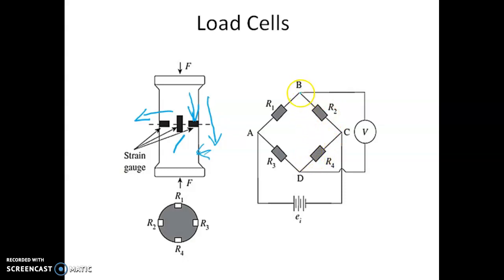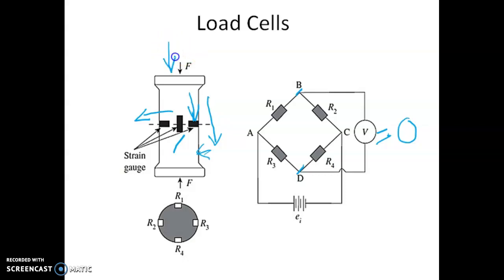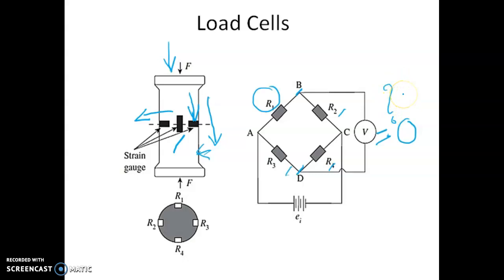The potential difference is taken between points B and D. When the elastic member is at the initial stage and not loaded, the potential difference will show a voltage equal to zero. When a compressive load is applied, the resistance values of R1, R2, R3, and R4 change, and this change is reflected as a voltage output. This output voltage is calibrated to show the corresponding force.